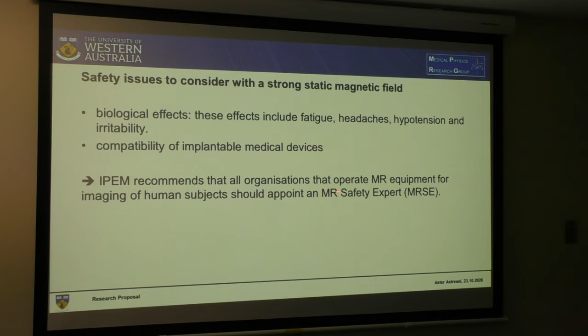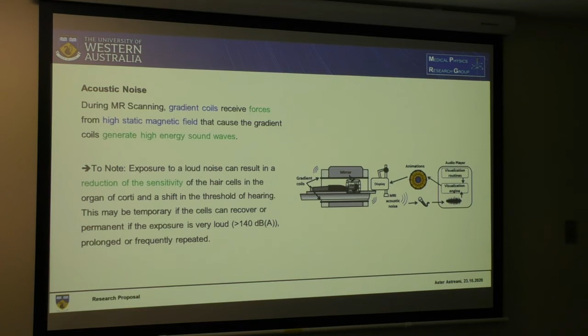So here we are talking about the acoustic noise. During MR scanning, the gradient coils receive forces from the high static magnetic field, which causes the gradient coil to generate high energy sound waves. Note that exposure to loud noise can result in a reduction of the sensitivity of the hair cells in the organ of Corti and a shift in the threshold of hearing. This may be temporary if the cells can recover, or permanent if the exposure is very loud, like more than 140 decibels, and also with longer and frequent noise.